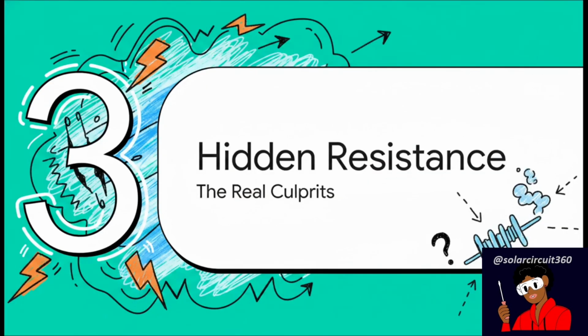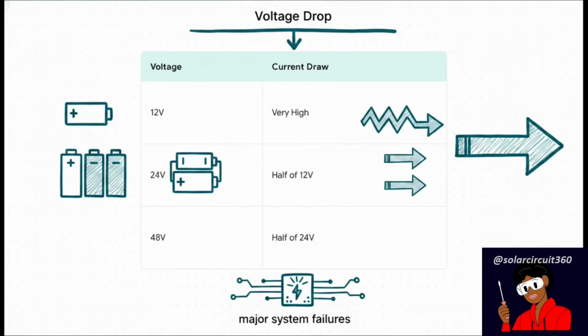All right, Section 3, Uncovering Hidden Resistance, the real culprits. To crack this case, we need to lean into a bit of hard electrical science and find the hidden resistance that's basically stealing your voltage. Check out this relationship. Current demand directly affects voltage drop. For the exact same amount of power, a 12-volt system pulls an incredibly high amount of current. Step up to a 24-volt system and you cut that current in half. Step up to 48-volt, it's halved again. But listen, on a 24-volt system, you are still dealing with some really hefty current draws. And high current is exactly what magnifies tiny electrical hiccups into total system failures.